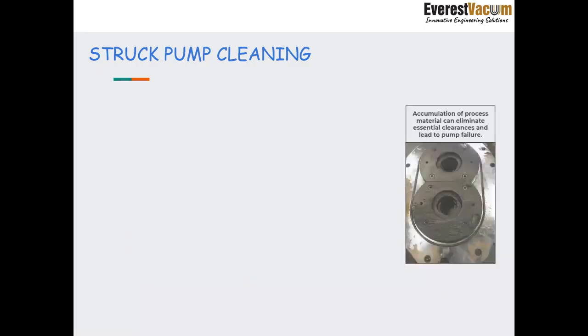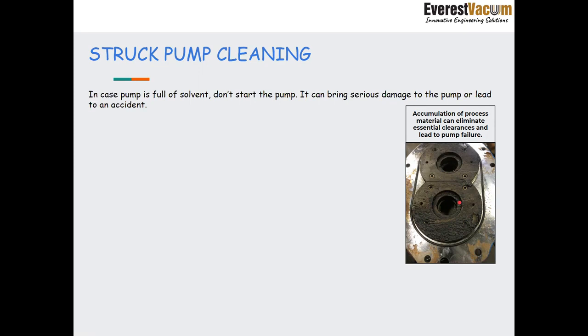Now, another problem that we have encountered in the process industry is that pumps get stuck. There is a lot of powder and carryover accumulation inside the dry screw vacuum pump. Now you can see in this figure, there is accumulation of process material, and what it does is it eliminates the essential clearances and leads to the failure of the pump. There's a lot of product buildup on this end plate. Firstly, we need to ensure that such a condition doesn't arise, because if this condition has arisen, it has already created a lot of damage to the pump.